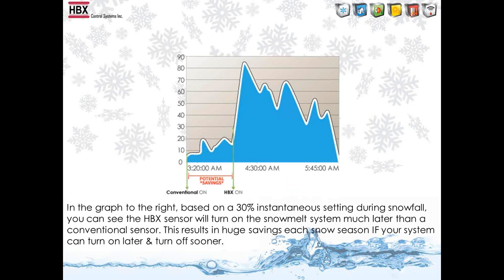So this is just a quick graph of some snow melt sensor readings that we did a few years ago. You can see on the graph that it's sensing a little bit of snow, under 10%. The snow goes up a little bit, it starts messing around, and then we had our intensity setting set at 30%. So it was at this point that it came out of idle and went into melt. If we had continued with only a little bit of snow and it went off, then we wouldn't have gone into melt mode in this case. So we would have saved a lot of money just from this period of time.